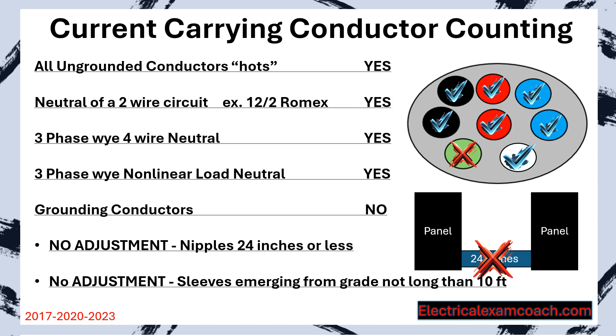There are no adjustments for sleeves emerging from grade that are not longer than 10 feet. For example, if you're doing a parallel 400-amp underground service using two sets of triplex, you've separated the triplex in the dirt so you don't need a bundling adjustment. But when you stub up to the panel, the answer is no adjustment is needed up to 10 feet — you can put them all in one conduit and stub up without doing a bundling adjustment.